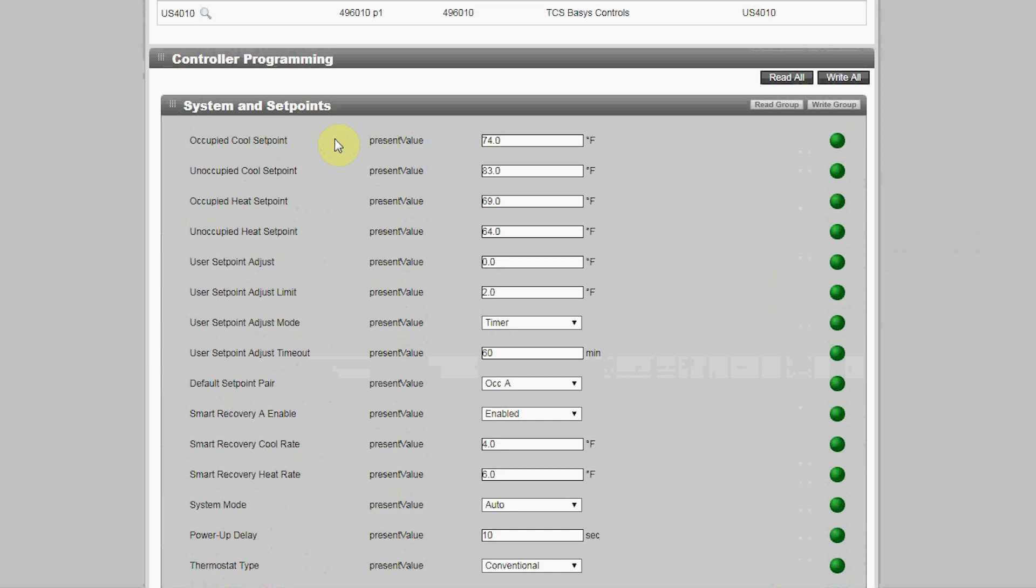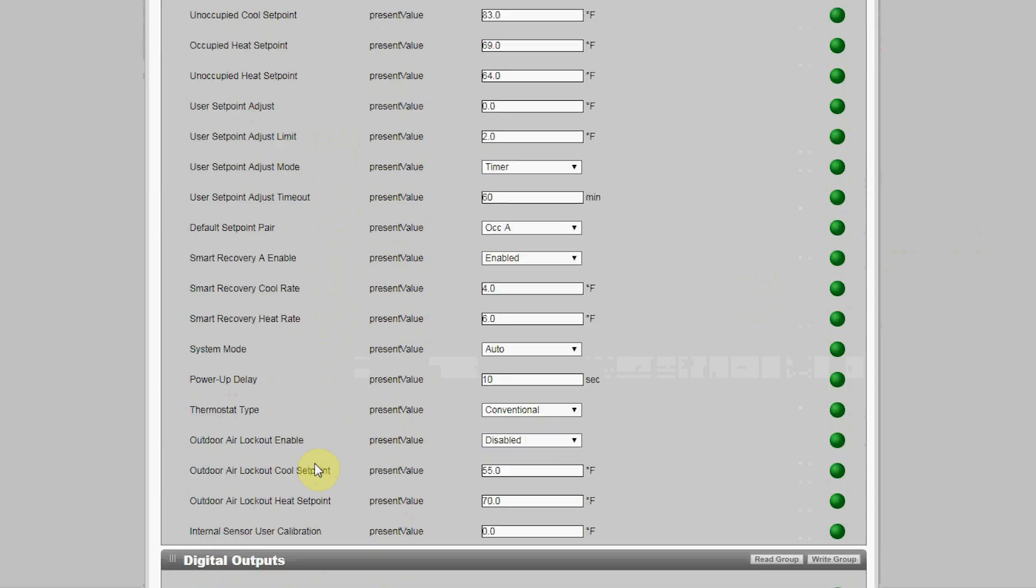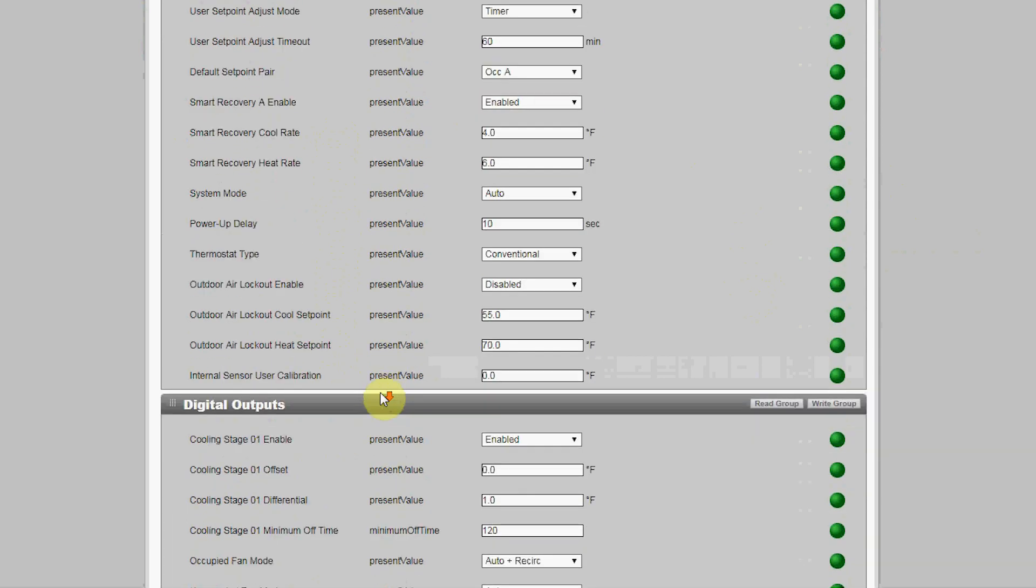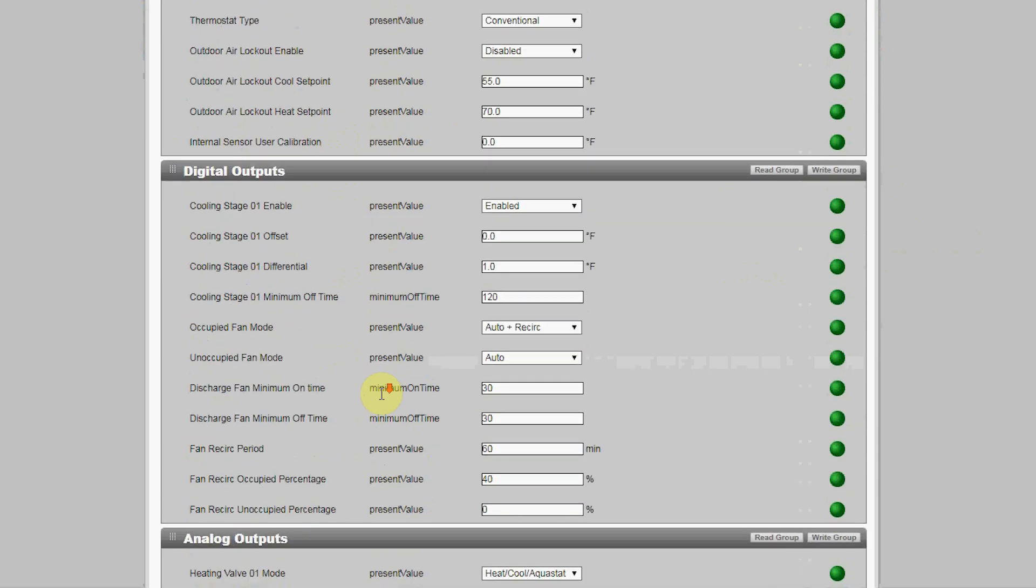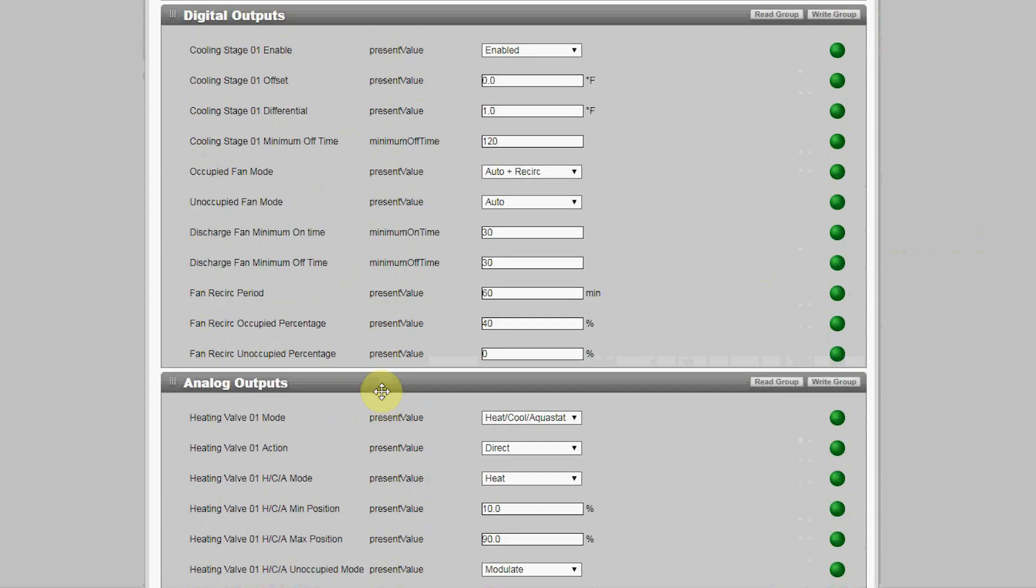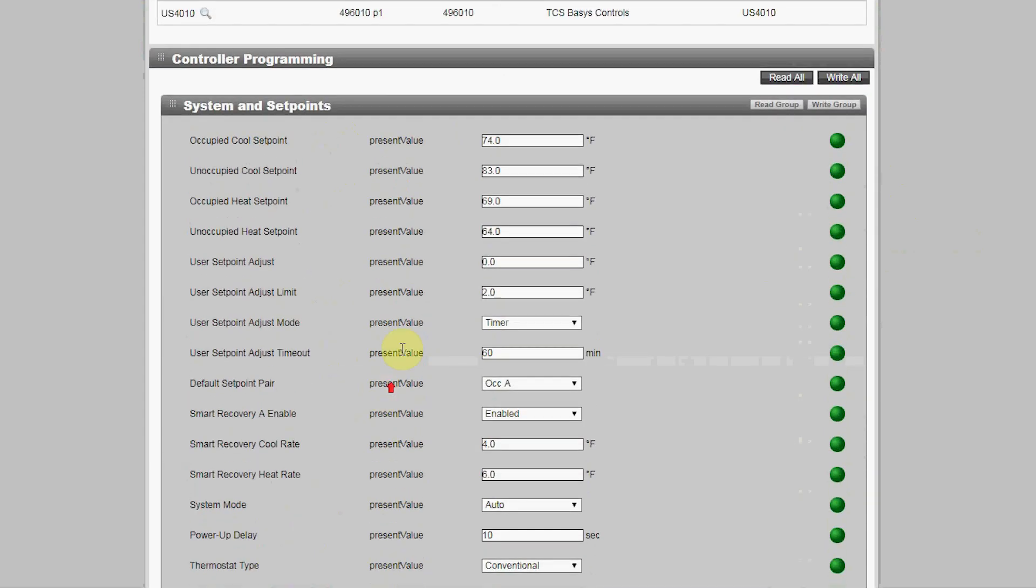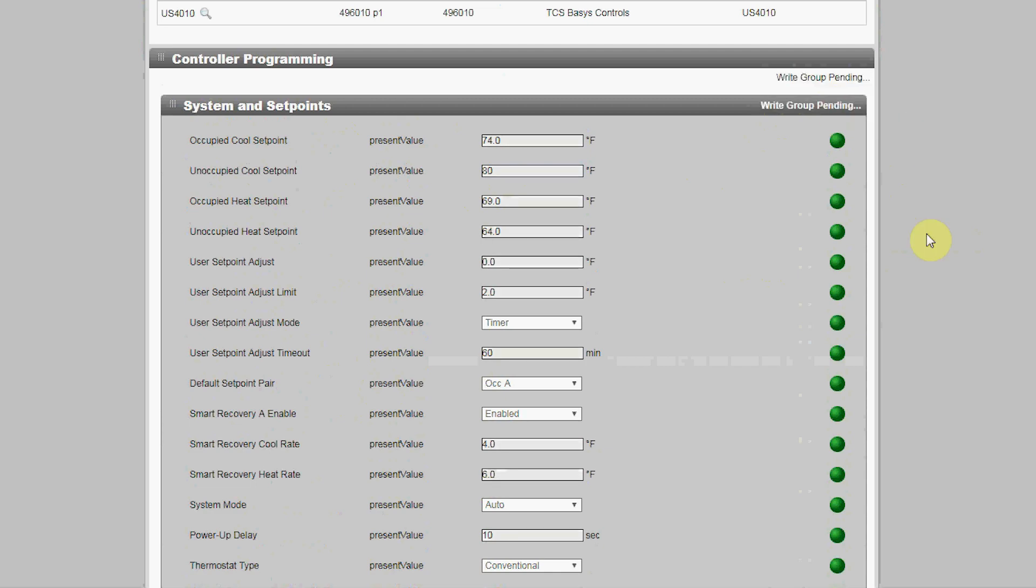Here they've been grouped into a group called Systems and Set Points, with all the set points and corresponding programming such as setpoint adjust limits, smart recovery, outdoor air lockout, then the digital outputs, analog outputs, and other functions are grouped as well. You can make a change, for example changing the unoccupied cooling setpoint to 80 degrees, and then just trigger a write to that group.